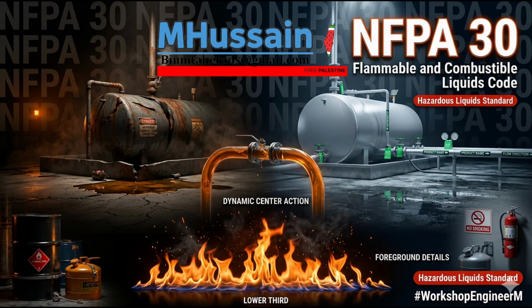The physical results of a BLEVE are just staggering. The structural failure of that seam essentially turns a massive steel drum into an unguided rocket. It really does. The bottom blows out, and the main body of the drum launches across the warehouse, trailing a huge concussive fireball. A flying steel drum weighing hundreds of pounds will easily shear right through structural support columns, and shatter the overhead sprinkler piping, instantly blinding the facility's primary fire defense system. You lose your suppression capabilities at the exact moment the fire load increases tenfold. It is an entirely unrecoverable scenario.